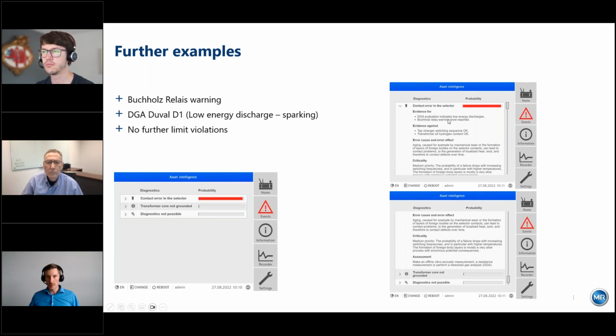First of all, we see that the low energy discharges, we see that the Buchholz relay warning level reached. We also see some evidence against it. And then we again describe what this error means, how critical it is. In this case, it's medium priority.